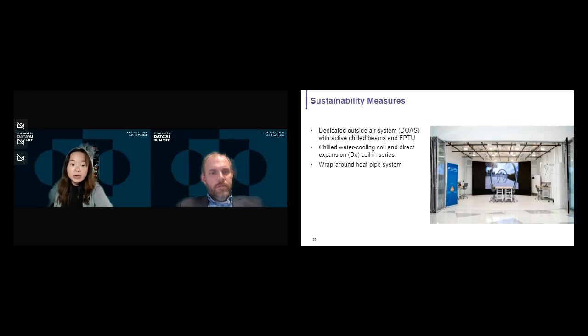As a summary for the final sustainability measure, after looking at the options, we have the dedicated outside air system (DOAS) with active chill beam and fan power terminal to balance constant volume and variable volume applications. We also have the chill water coil and DX coil in series with the wraparound heat pipe as our energy recovery system.